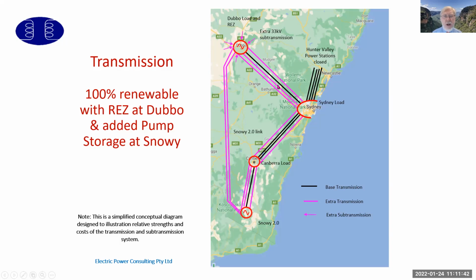We're doing it over longer distances with much greater redundancy because we know that these renewable energy zones are operating at capacity factors down around 25 to 30%, compared to coal plants, which can get up around 60 and 70%. So that's reflected in the overbuild of the transmission grid.